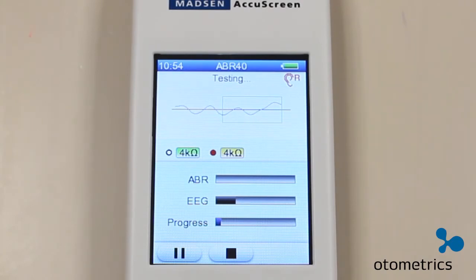The ABR bar shows the amount of ABR data collected. This bar will grow progressively as more and more data is collected and an increasingly stable statistical measure is calculated. Note that this bar may also decrease if a lot of noise is present during the test. The EEG bar indicates the electrical noise level in the data. For example, myogenic noise should be as low as possible.